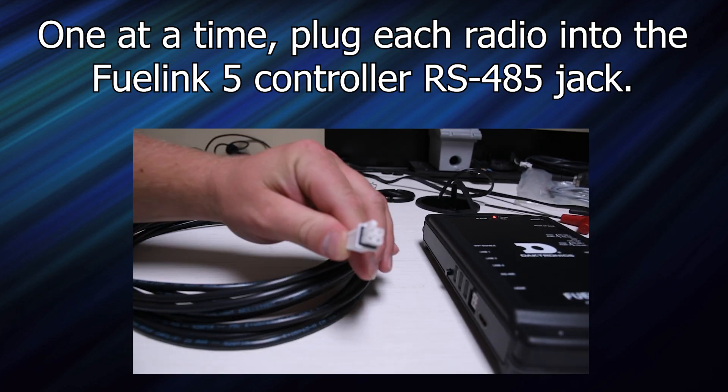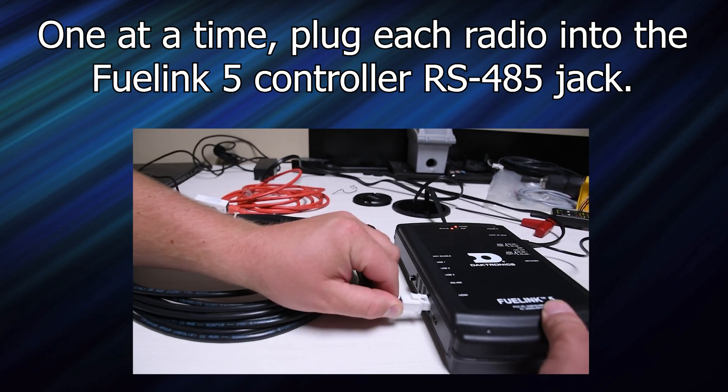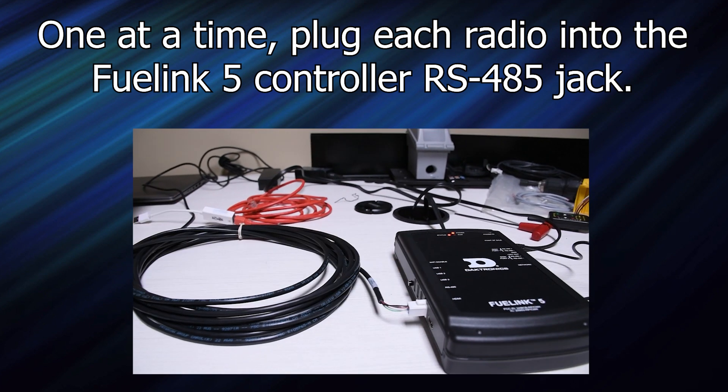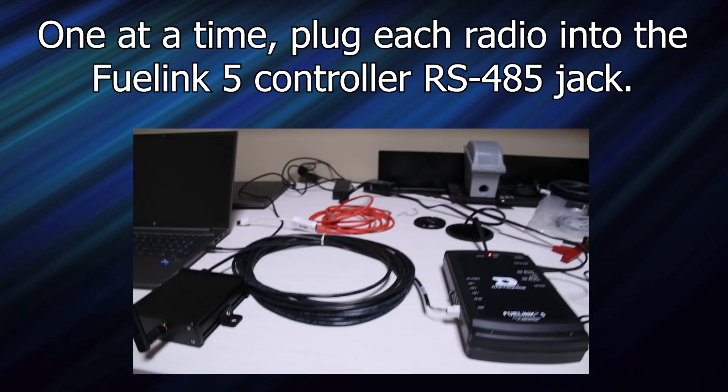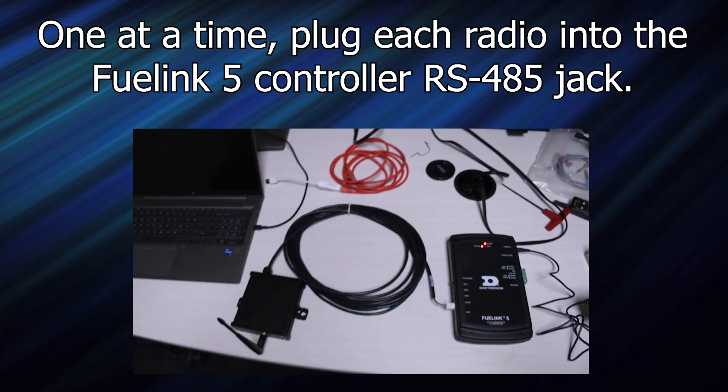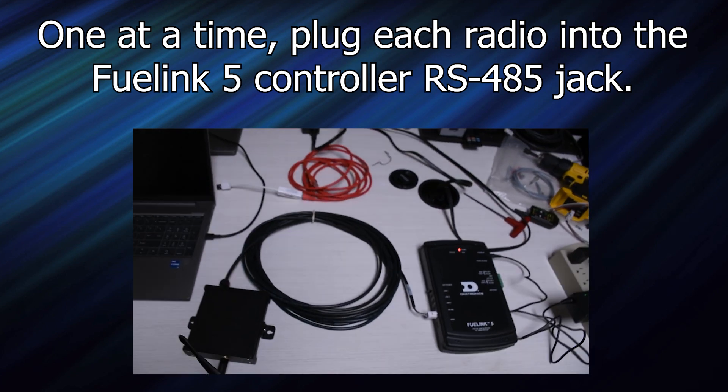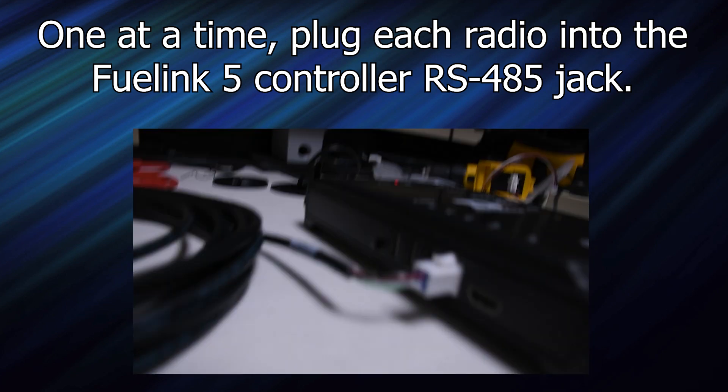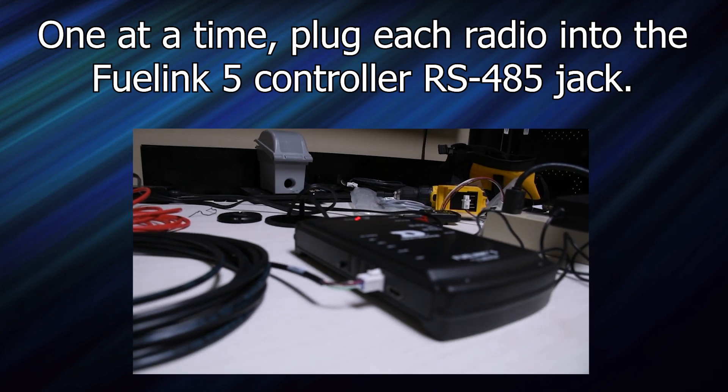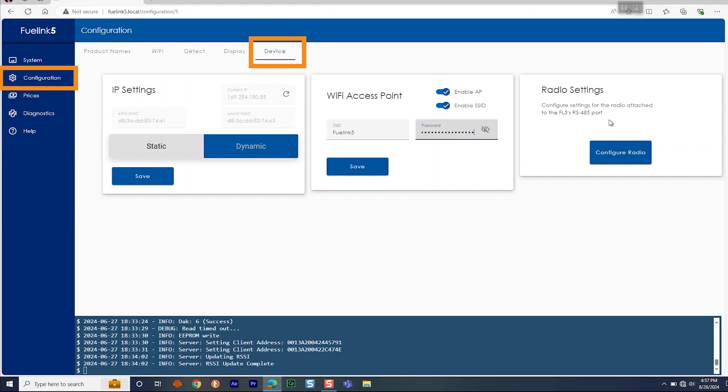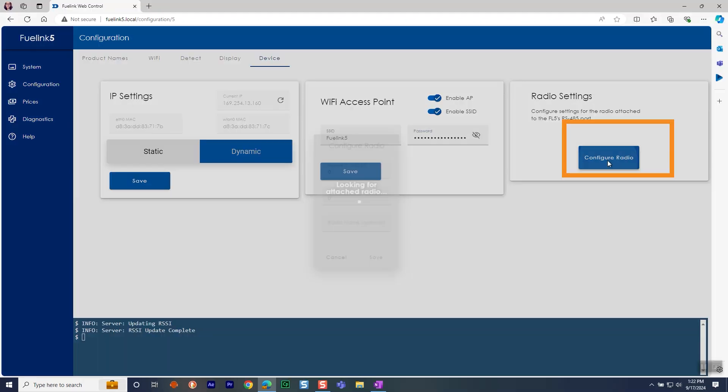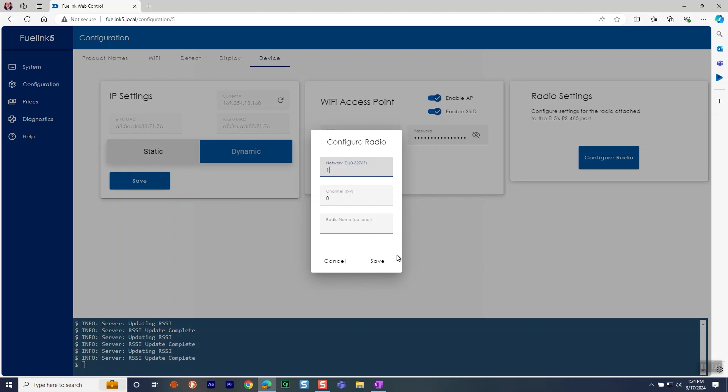Once in the user interface, you can now configure the radios. One at a time, plug each radio into the FuelLink 5 controller at the RS-485 jack. In the software user interface, navigate to Configuration, Device, and then click Configure Radio.